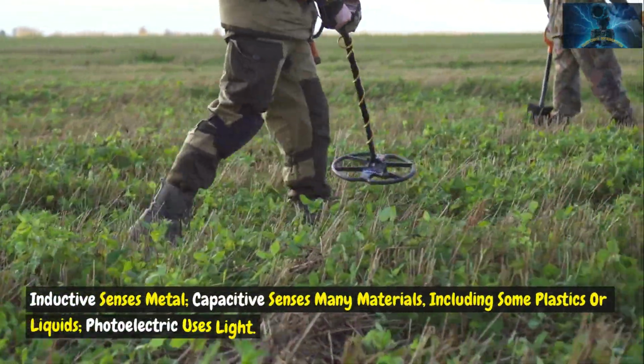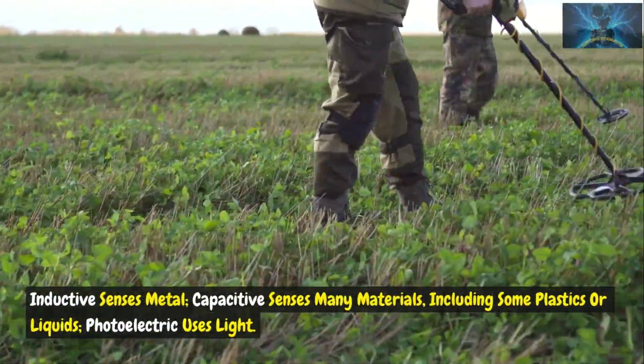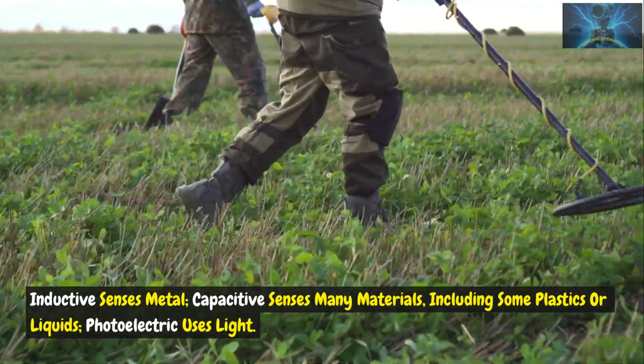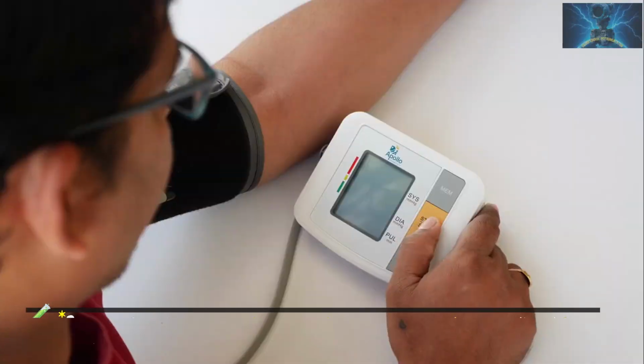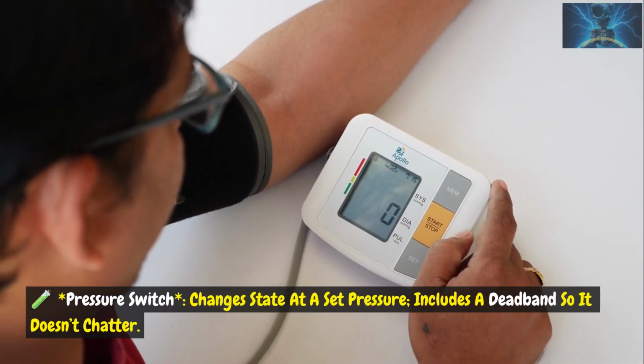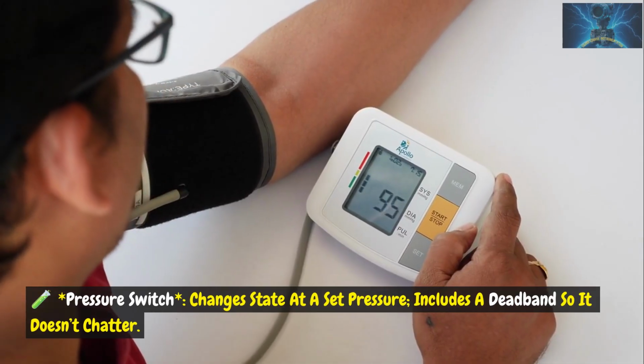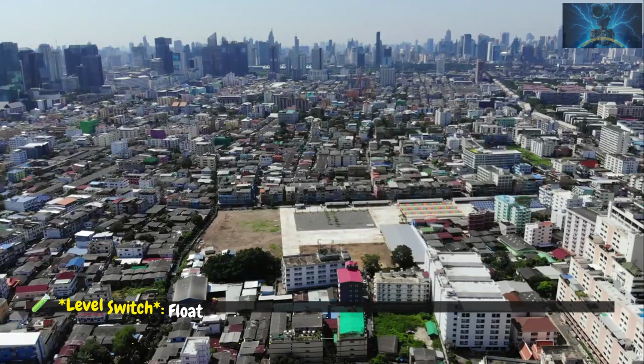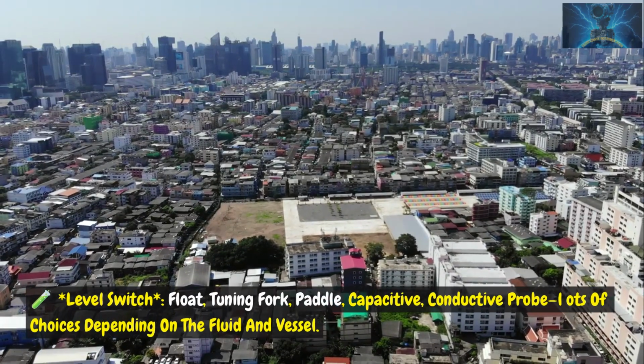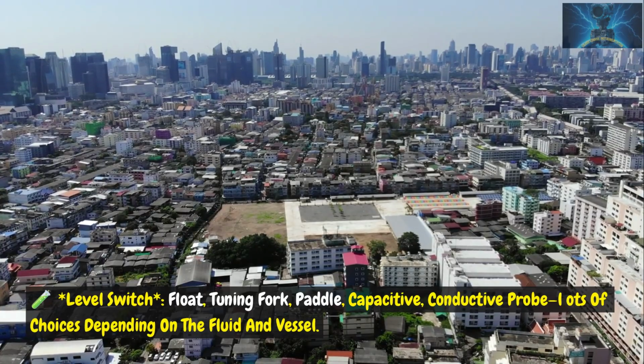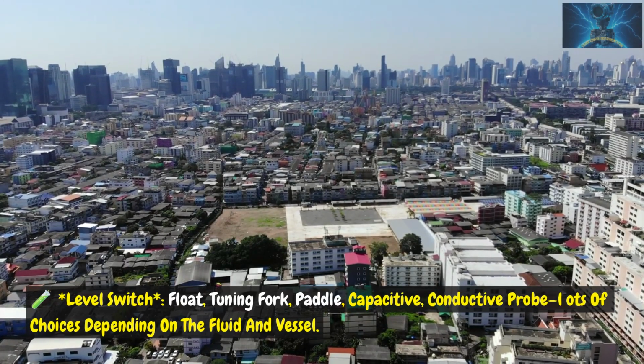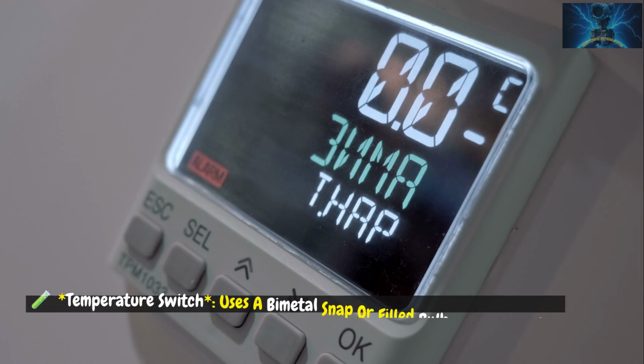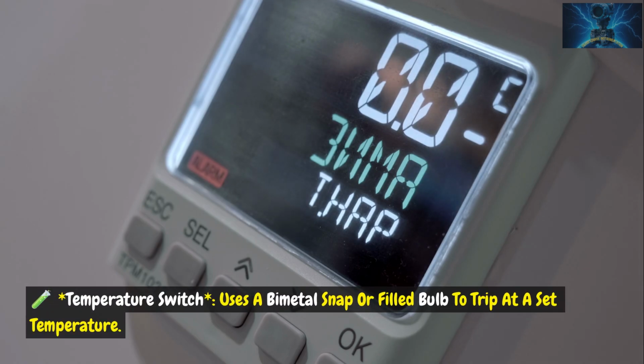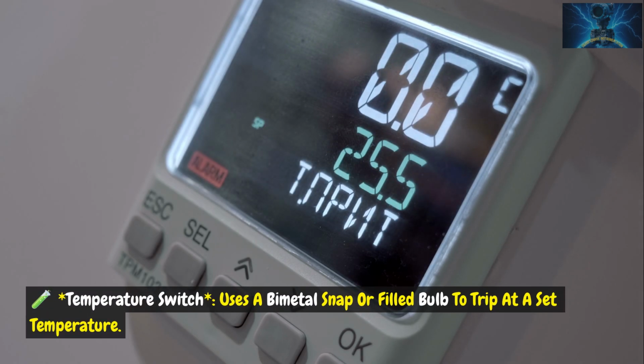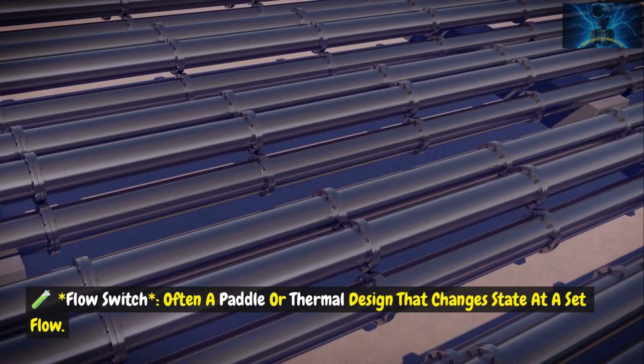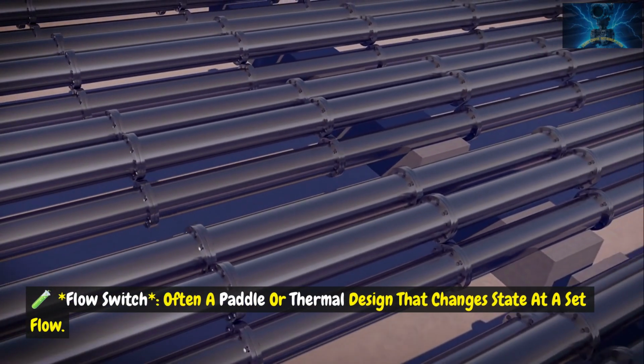Inductive senses metal. Capacitive senses many materials, including some plastics or liquids. Photoelectric uses light. Pressure switch: changes state at a set pressure. Includes a dead band so it doesn't chatter. Level switch: float, tuning fork, paddle, capacitive, conductive probe. Lots of choices depending on the fluid and vessel. Temperature switch: uses a bimetal snap or filled bulb to trip at a set temperature. Flow switch: often a paddle or thermal design that changes state at a set flow.